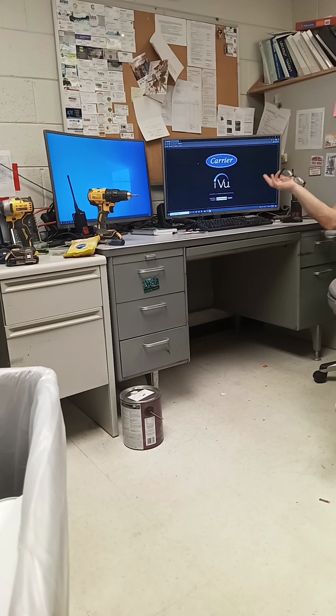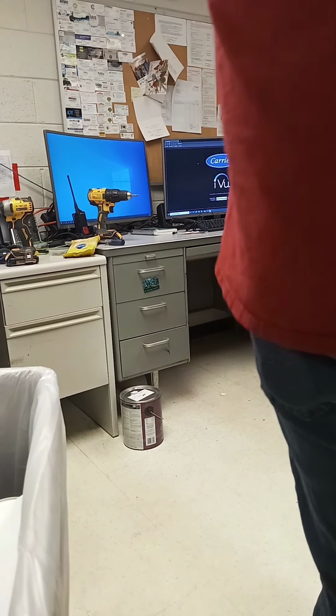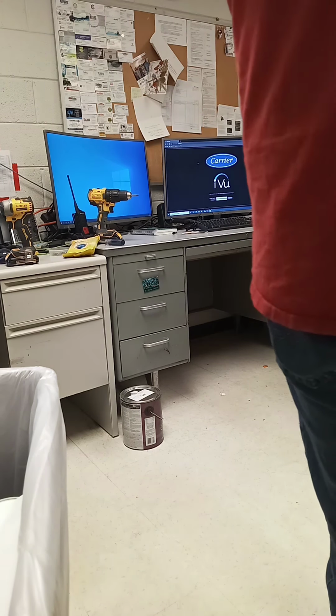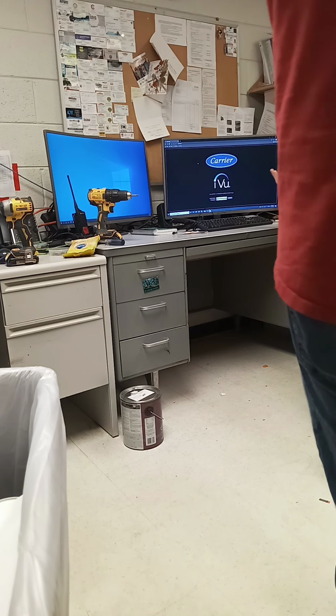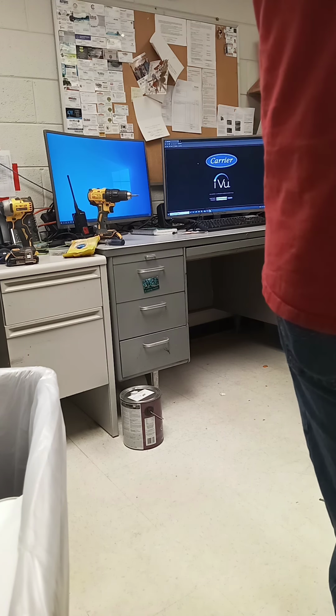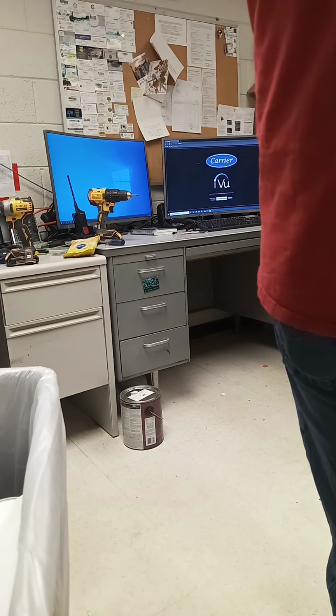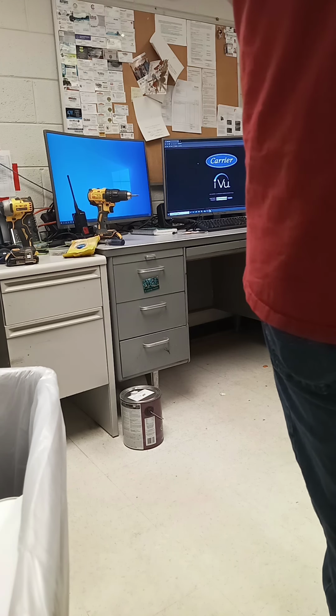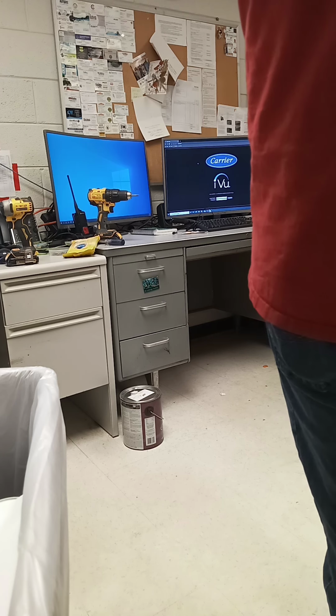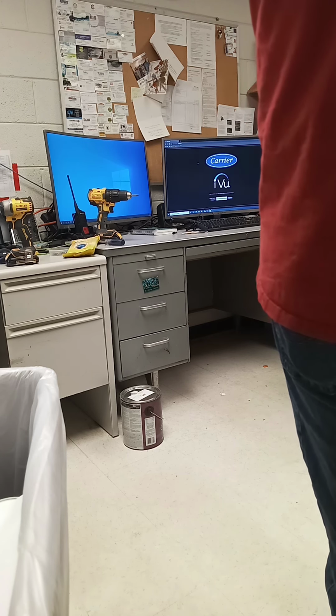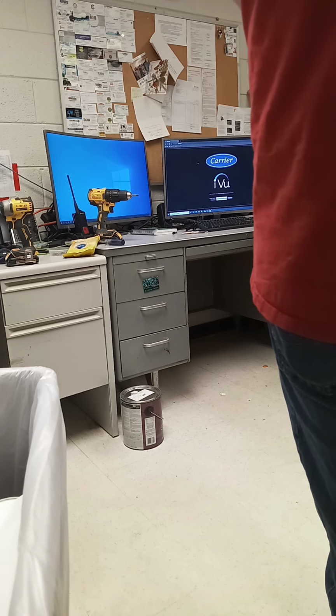It's an agnostic server sitting in your building, and it can do multiple buildings. We've got them doing entire campuses. I could put a building in France on this one server over here as long as I can get IP exchange between those two buildings. So it's basically an Ethernet device that connects to the network, and then we have BACnet routers that bring the information in from pieces of equipment.